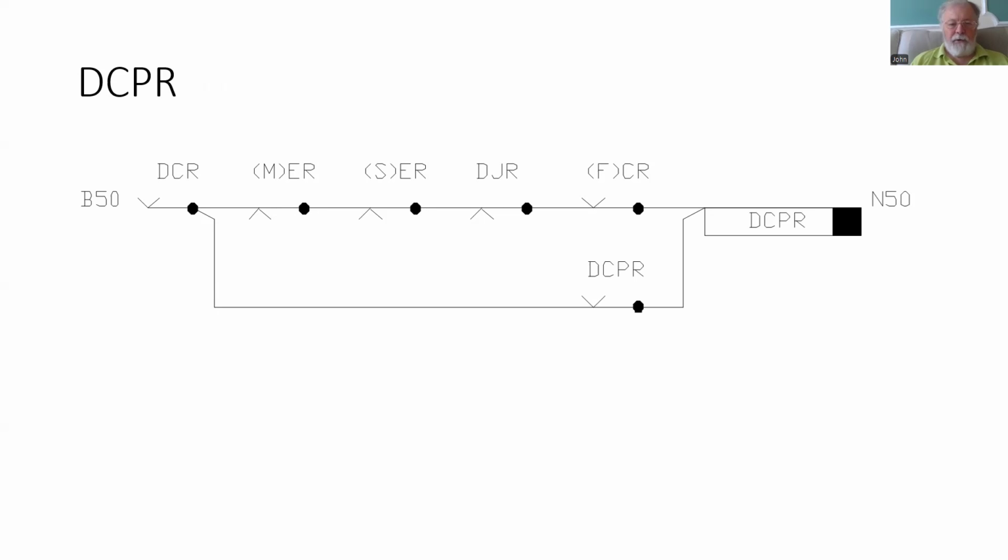Not an uncommon fault on push-button panels is with the buttons, and either they can be stuck in or they can fail to register. And buttons stuck in will lock up the PBI. With the DCPR energized, it will then seal in over its own contact until the DCR drops.